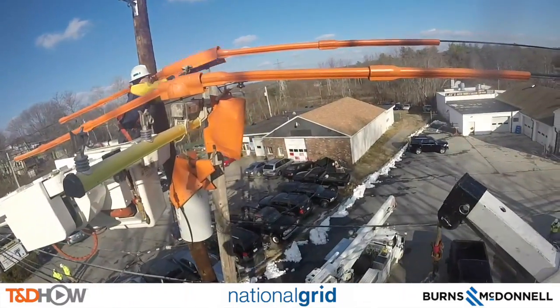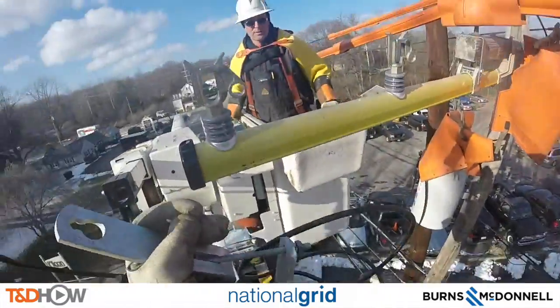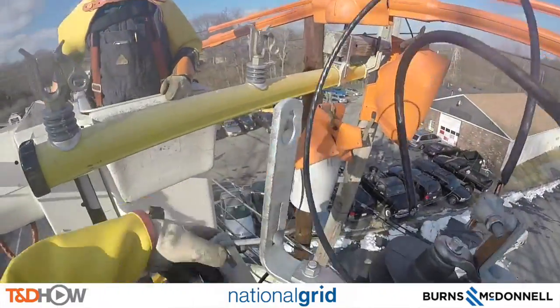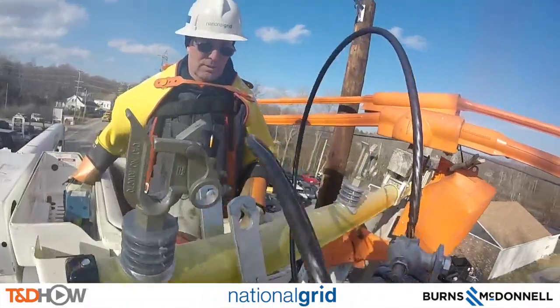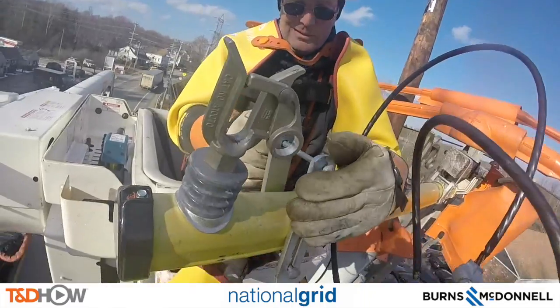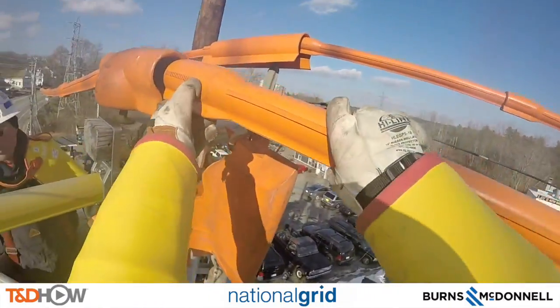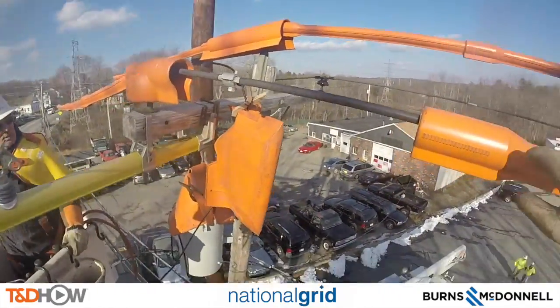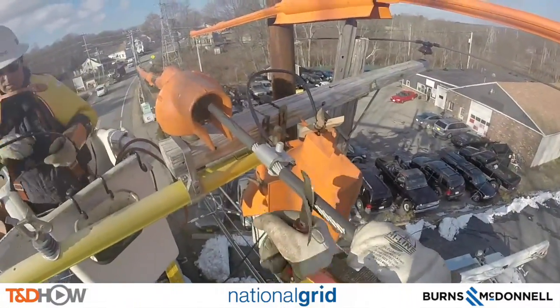The next task is to hang a new fuse or switch cutout on this temporary cross arm — you'll see them do that. There's a new switch right there. Now they do take away the old switch, but we're not showing that for time purposes here on this video. Instead, I'm going to show you the connection to the line for the new switch they've just hung.